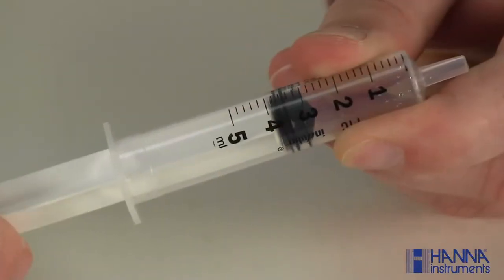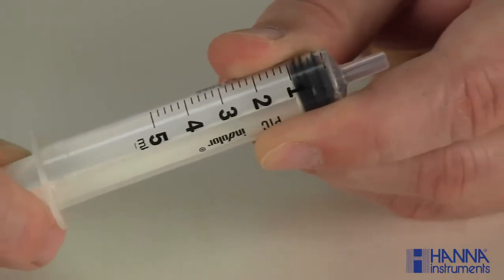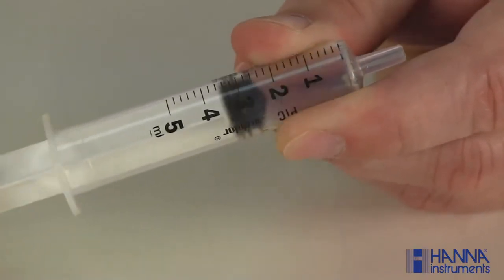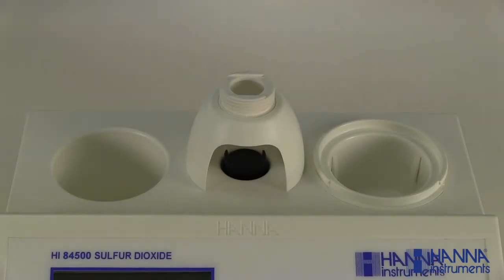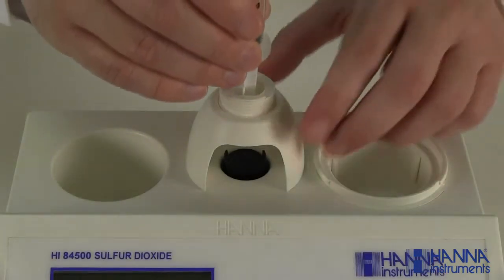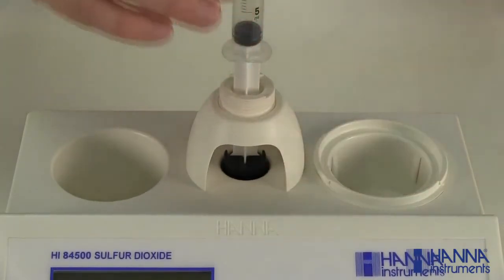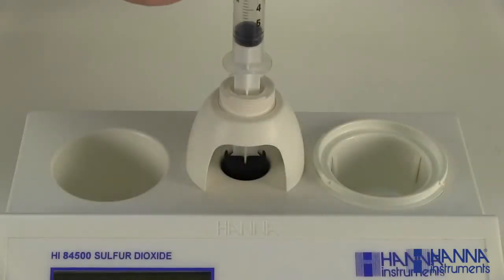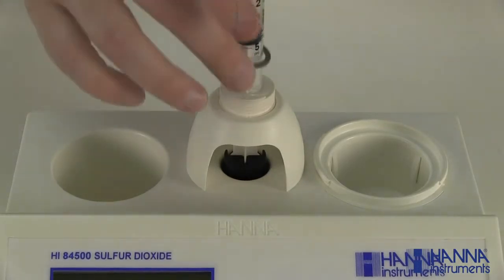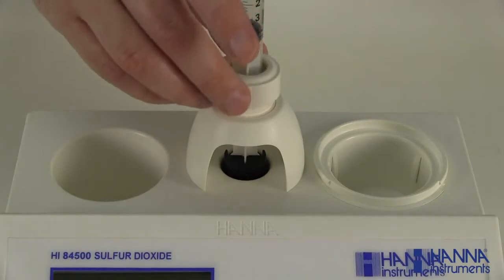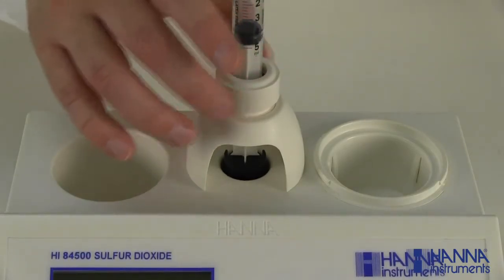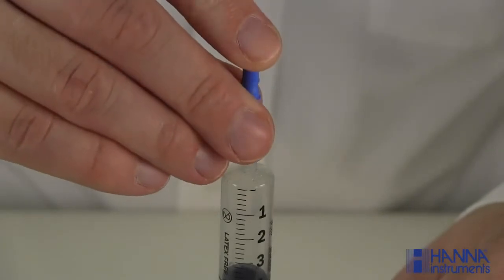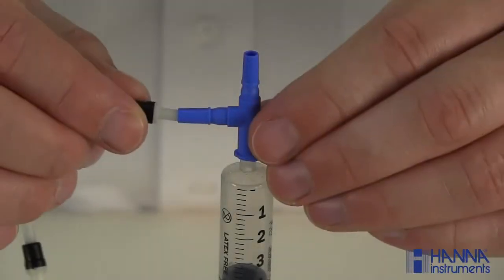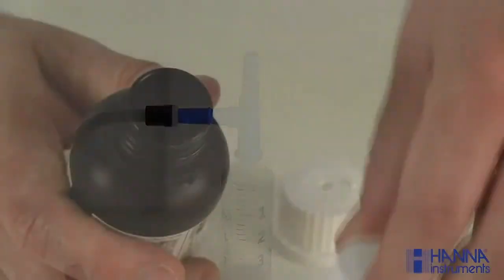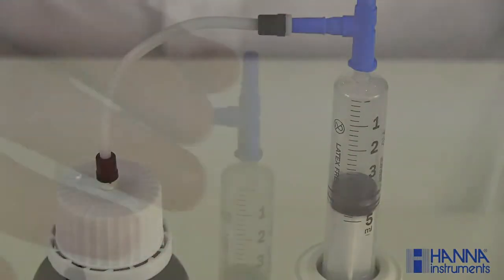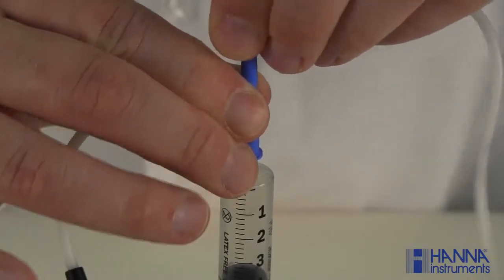Pump installation. To install the dosing pump, extend the plunger on the 5 milliliter syringe to its maximum volume. Place the syringe in its dedicated spot on top of the titrator. Be sure to arrange the bottom of the syringe into the holder on the pump and lock it into place. Once in place, lower the barrel until it sits flush on the holder. Put the O-ring and fixing nut over the syringe and turn clockwise to secure in place. Place the valve on top of the syringe and ensure it fits securely. Insert the aspiration tube into the left side of the valve and replace the titrant bottle cap with the attachment cap. And finally, insert the dispensing tube into the top of the valve.